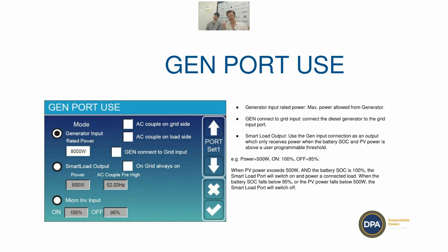This is just another contactor-controlled connection to the AC bus. And so it can be used for a generator, or it can be used for an AC-coupled inverter if you're off-grid or on-grid. And it can be used for smart loads and things as well. If you're off-grid, you don't have to use the generator port for the generator. You can use the grid port for the generator. And if you do that, in this menu here, you just tick here, gen connected to grid input.